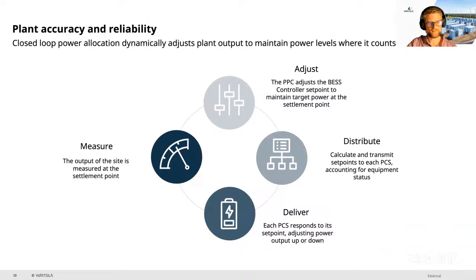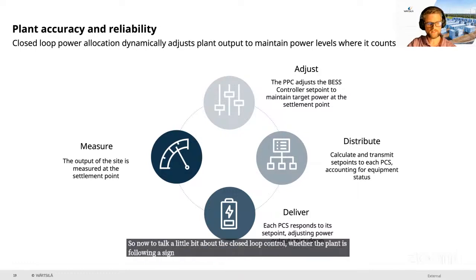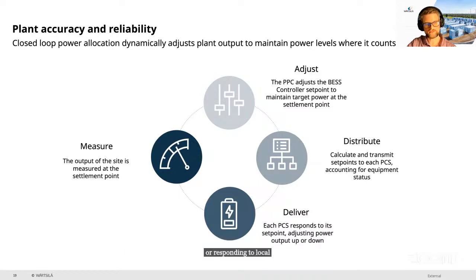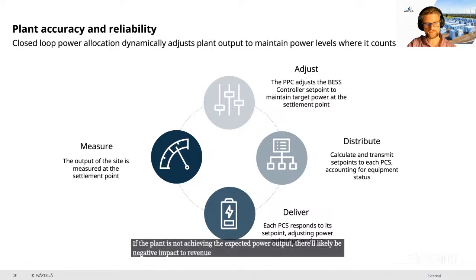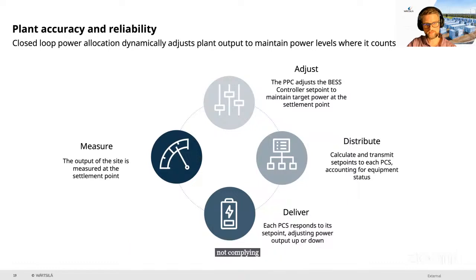Now to talk a little bit about closed loop control. Whether the plant is following a signal in a wholesale market, responding to local measurements in frequency markets, or performing grid forming functions, the PPC has to be able to maintain accurate power at the point of interconnection. If the plant is not achieving the expected power output, there will likely be a negative impact to revenue, and potential penalties for not complying with local grid code or market rules. The most reliable method for ensuring an accurate response is a properly tuned closed loop controller, and typically that's going to be using a PID.